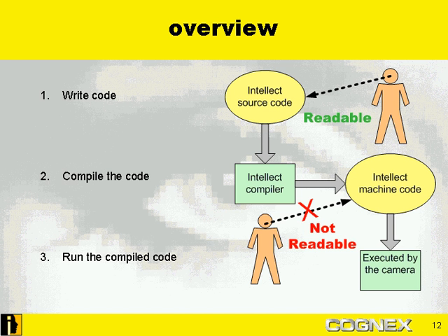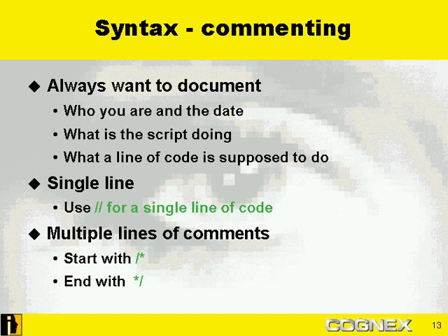But every time you open up that script editor, you see this code. So if you make a change to it and don't compile, those changes never made it into machine code. So your script will be running, but it'll be running on an older version. So it's something to be aware of. It becomes a force of habit. You just kind of always hit the compile button before you get done editing or exit the editor.